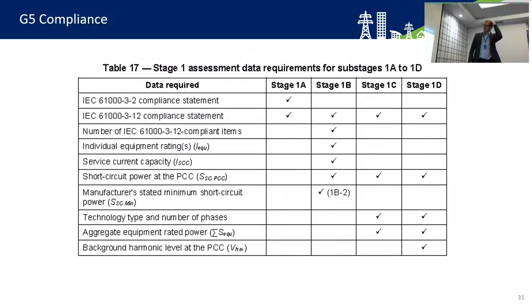There's no guarantee it will pass with stage 1D, because if we measure the backgrounds and they're quite a high level, it means you're probably only going to be able to connect one or none to the network. With non-compliance, you may then have to go away, do a HV supply, and fit filtration. It could be quite an expensive job.